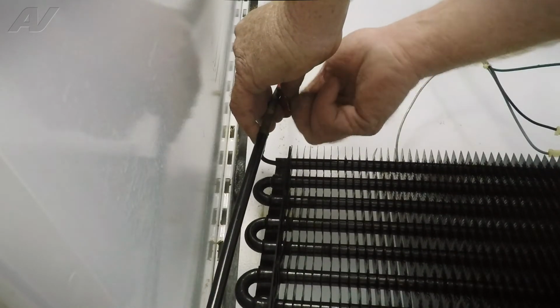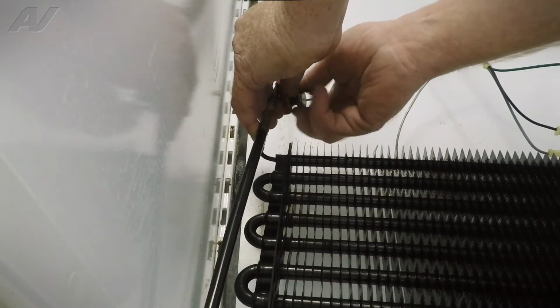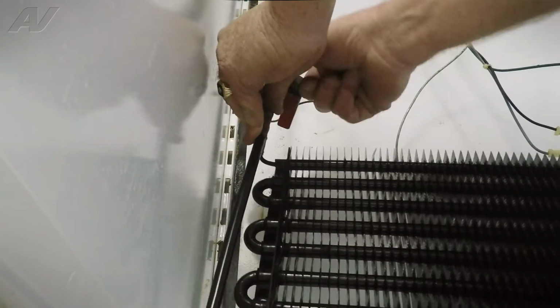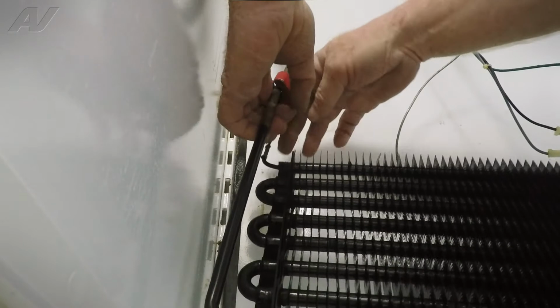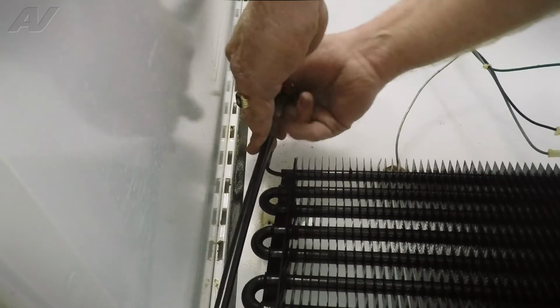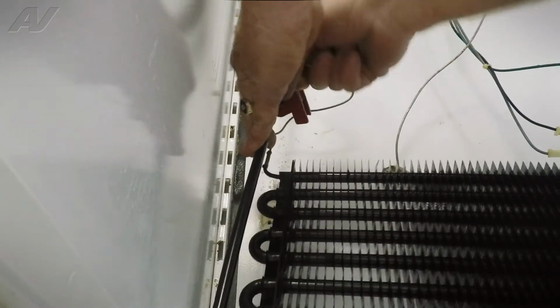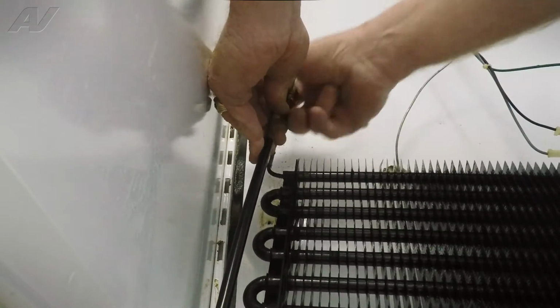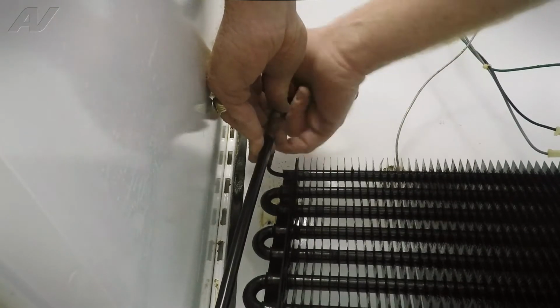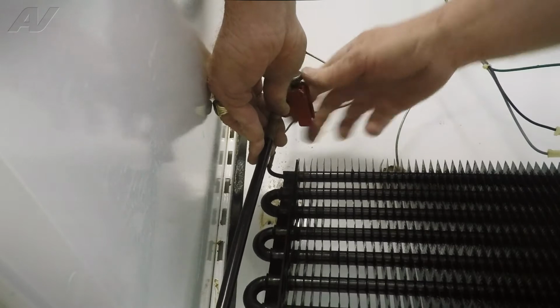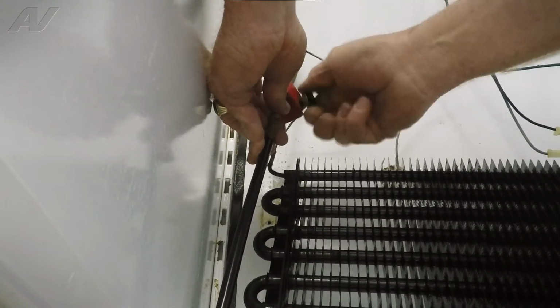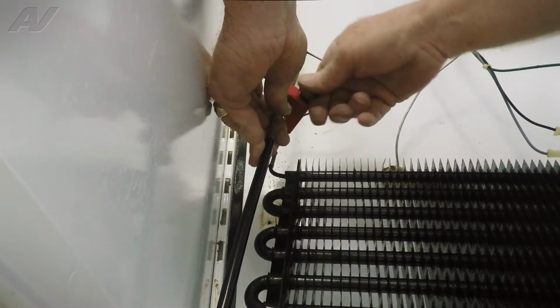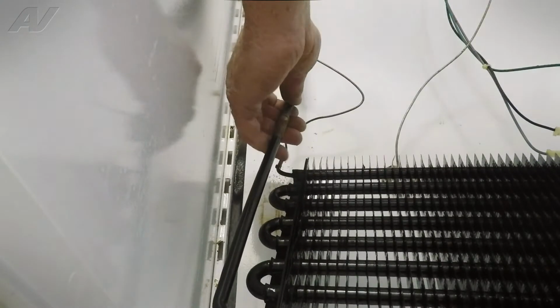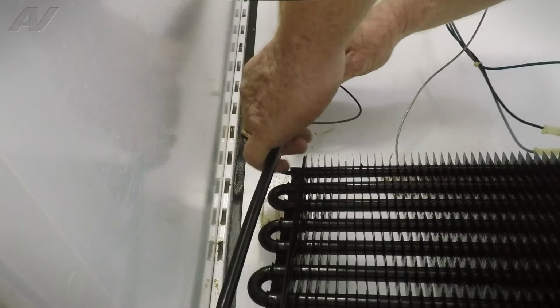So we'll get our tubing cutter on the pipe and tighten it down. And you want to snug it, and then rotate your tubing cutter around. And then when it feels loose to turn, snug it again. You're going to keep snugging it as it loosens. And that little blade will cut through the tubing for you. Now, take the tubing cutter off and pull the tube apart.